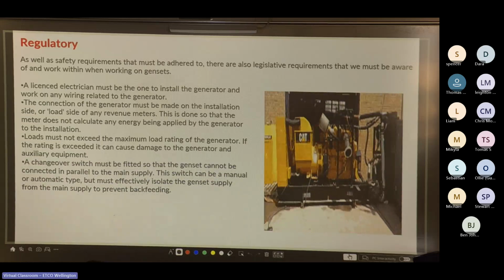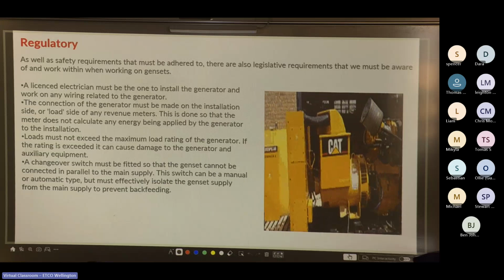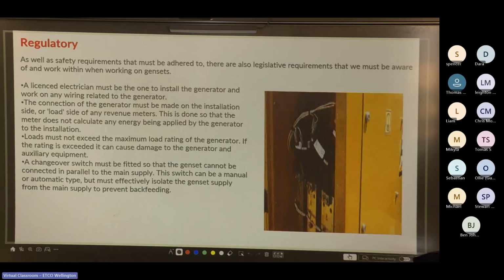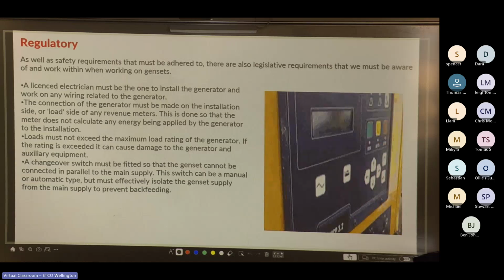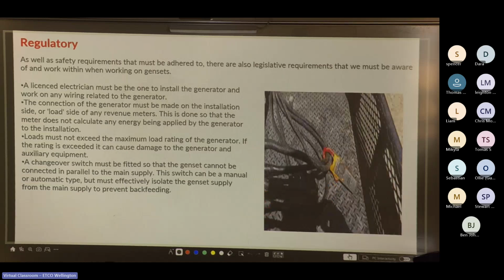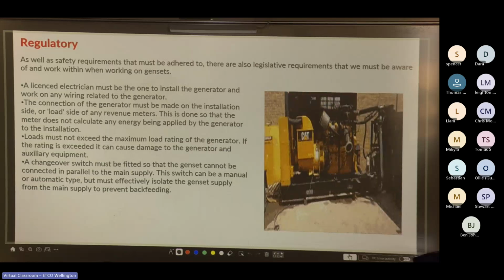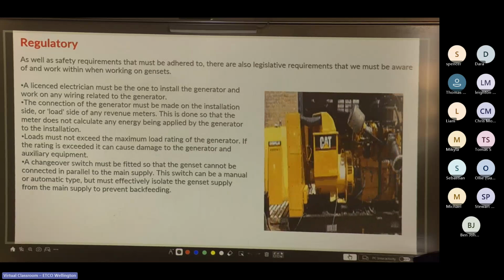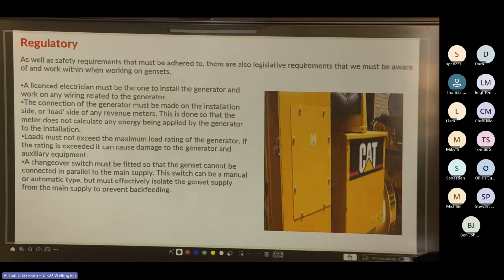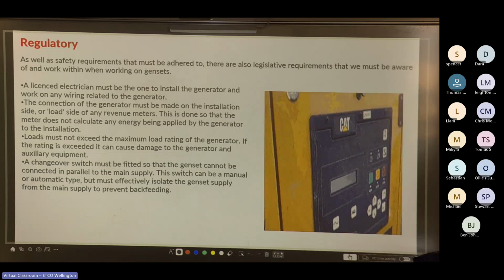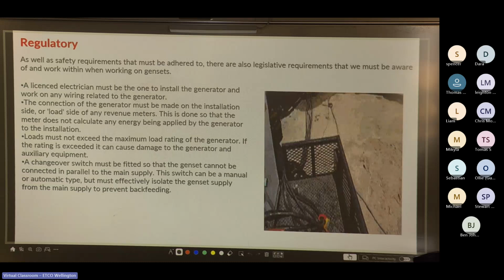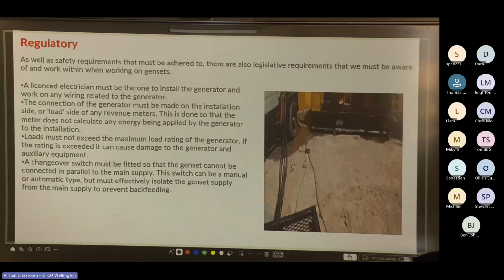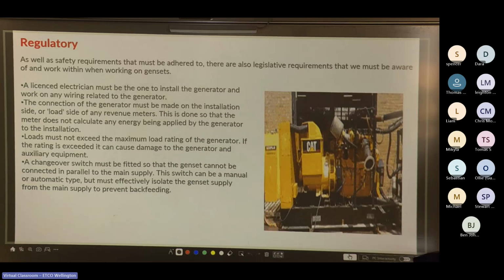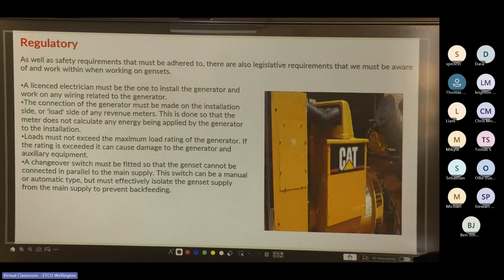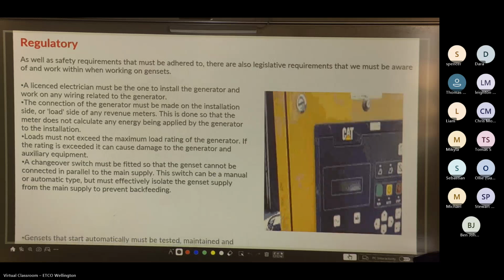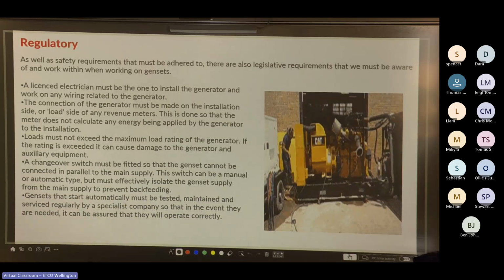A changeover switch must be fitted so the genset cannot be connected in parallel to the main supply. The switch can be a manual or automatic type, but must effectively isolate the genset supply from the main supply to prevent backfeeding. One way to do this is to have a no voltage relay and contactor set up, or changeover contactor. That way, if the mains are connected, the contactor stays closed to allow the mains to run through. But if the mains drop out, the contactor releases and transfers the power over to the generator. Or just a big transfer switch.